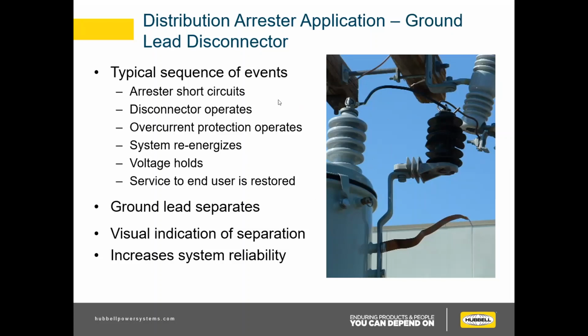So, kind of got off track there, but a typical sequence of events: for whatever reason, the arrestor short circuits. It conducts too much current for too long a time, and the disconnector operates, and you get this. The ground link falls away. The overcurrent protection operates, whether that's a fuse cutout or a recloser, and the system will re-energize, the voltage will hold, and then service is restored to the end user. Like I said, your lights will flicker once, but it's not going to lock everything out. So the ground lead separates, you have a visual indication of separation, and that increases your system reliability.